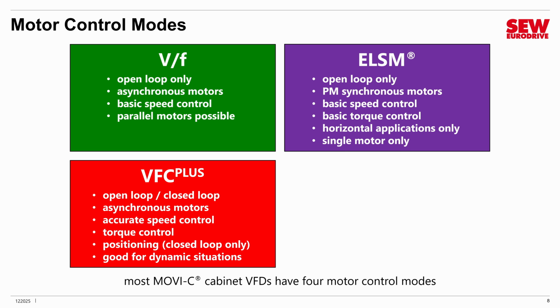The third motor control mode is ELSM, which stands for Encoderless Synchronous Machine. It was introduced by SEW-Eurodrive with the MOVI-C portfolio. It is an open loop only mode for permanent magnet synchronous motors, commonly called servo motors. In the past, it was often very difficult to run a servo motor open loop, but ELSM solves that little problem. It gives you good basic speed control and basic torque control. It's only suitable for horizontal applications, and you can only run a single motor. You can't put them in parallel. But if you're using a servo-type motor for a speed control mode, it's an excellent choice because you can save the money and not put an encoder on that motor.